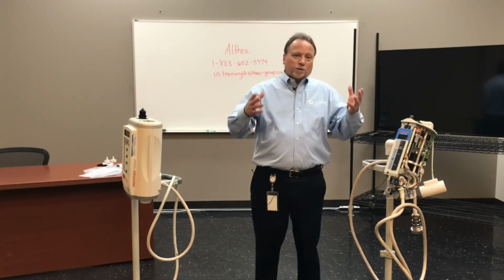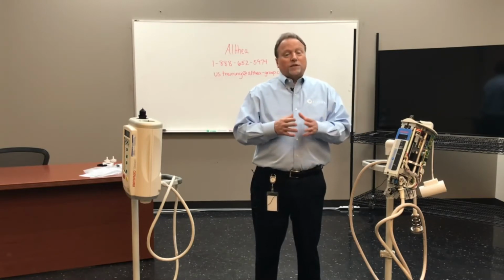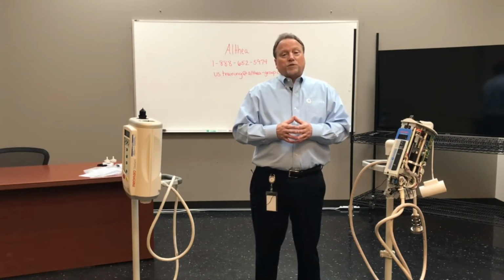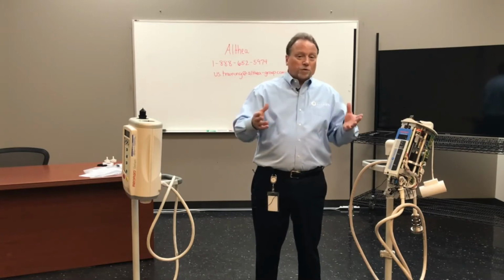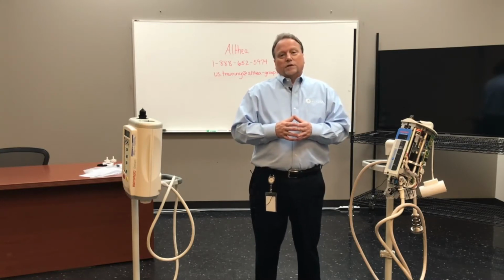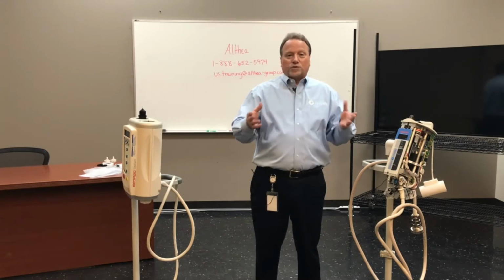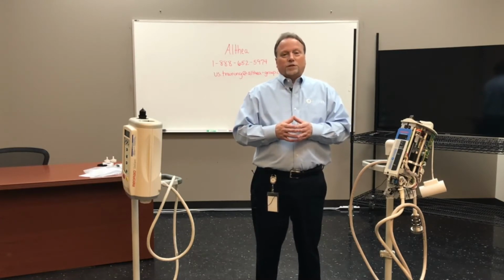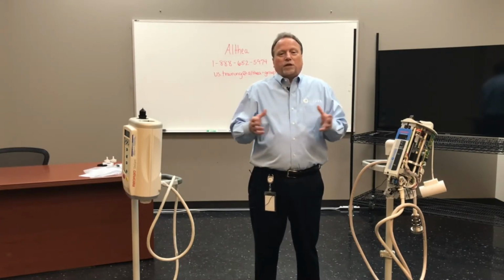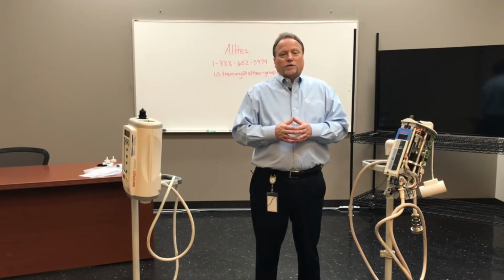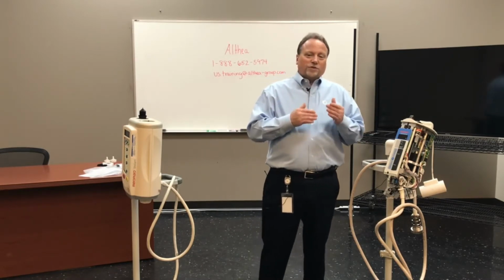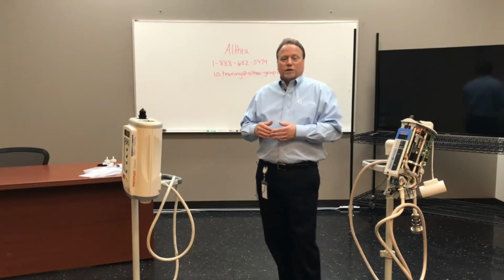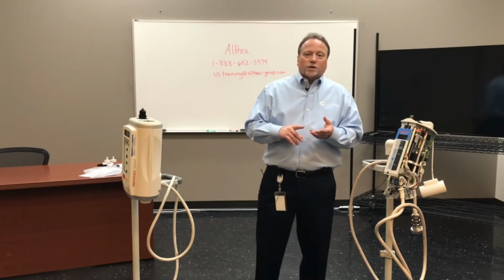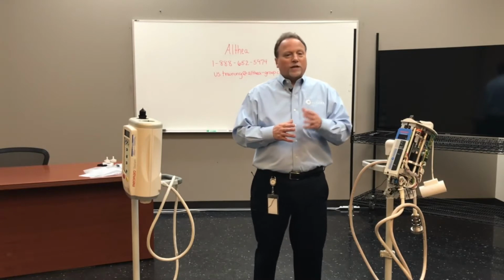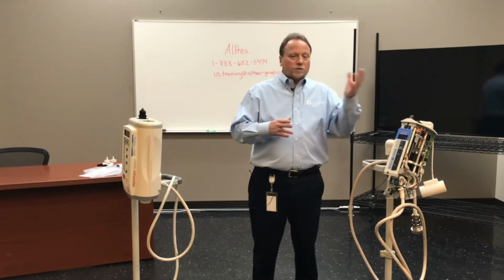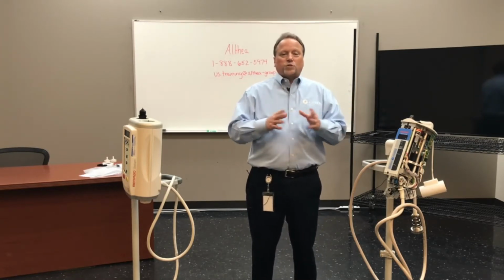Is all the PM pretty much the same on all the injectors? Yes, it is. Are PM procedures basically the same on all X-ray equipment? Yes, it is. Are PM procedures the same on all infusion pumps? Yes, it is. Doesn't matter what manufacturer you're working on. You still have set things that you have to do. On X-ray equipment, you've got linearity, accuracy. You have those things that you have to verify. Infusion pumps, you have flow rate, occlusion, pressure, whatever it is.